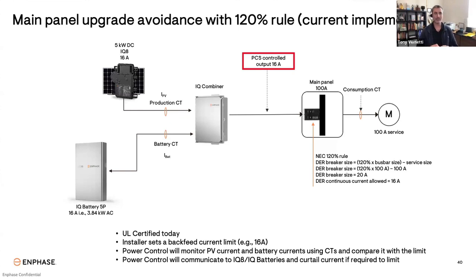According to this rule, in this example with a 100 amp panel, the backfeed breaker can be 20 amps at a maximum. So with 80% loading, the maximum current allowed is 16 amps, which is about a 5 kilowatt PV system. It's a smaller system than most homeowners need these days. With PCS implemented, the Enphase system can control the output of solar and battery so it never exceeds 16 amps. This means that you can install more solar capacity. In this example, we have a 6.2 kilowatt PV system, which has a 20 amp rating. Most of the time, this isn't an issue, as the solar PV system is usually producing well under 20 amps.